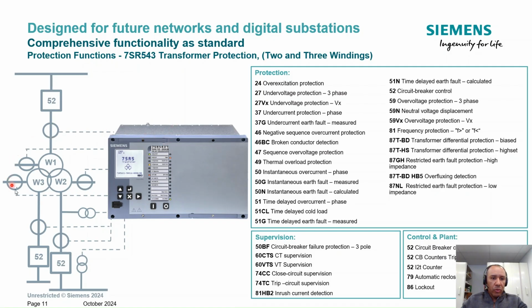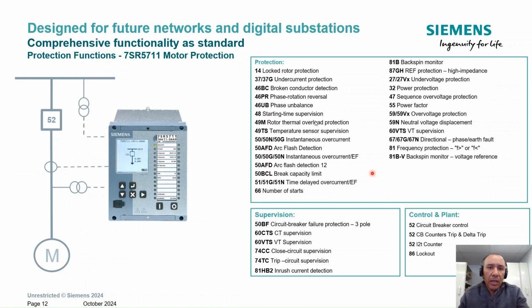These are very typical solutions when we talk about renewable power plants. You can perform the protection for the 3 winding transformer. Definitely, if this device is a transformer relay, we have the transformer differential on this device as well. Also, you can perform backup protection like 50, 51 per each leg: the incomer and the 2 outgoings, or the 2 collectors and also the outgoing here. It depends if it's a generation or load. And the supervision of the trip coil and close coil, and the control of the circuit breakers, is possible as well.